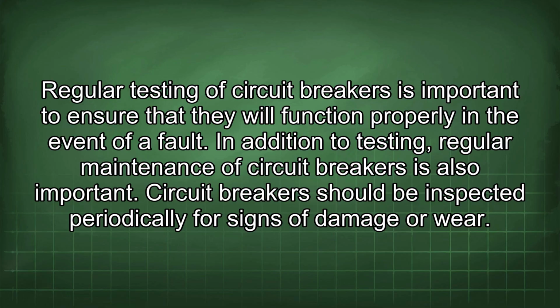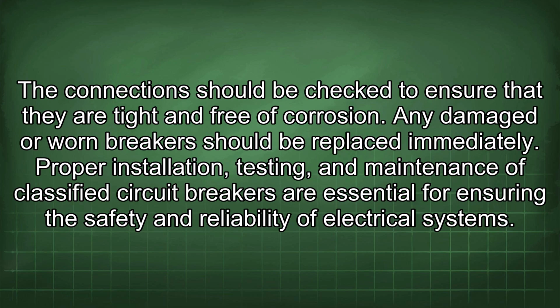In addition to testing, regular maintenance of circuit breakers is also important. Circuit breakers should be inspected periodically for signs of damage or wear. The connections should be checked to ensure that they are tight and free of corrosion. Any damaged or worn breakers should be replaced immediately. Proper installation, testing, and maintenance of classified circuit breakers are essential for ensuring the safety and reliability of electrical systems.